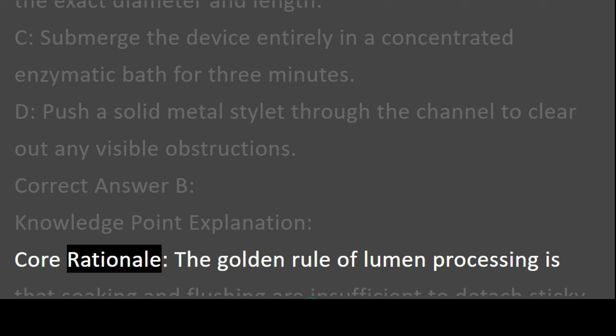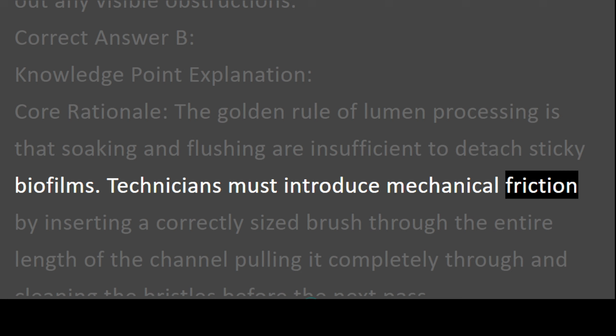Correct answer B. Knowledge point explanation. Core rationale. The golden rule of lumen processing is that soaking and flushing are insufficient to detach sticky biofilms. Technicians must introduce mechanical friction by inserting a correctly sized brush through the entire length of the channel, pulling it completely through and cleaning the bristles before the next pass. Trap analysis. Option A.